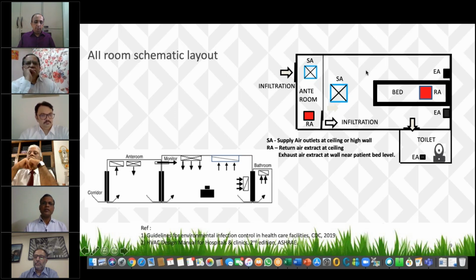But normally, hospitals have maybe 1 or 2 or 3 rooms which are designated and built to perform like an airborne infection isolation room. In today's case, where we have more cases, more patients requiring AII, that is airborne infection isolation, it may not be possible to bring all the patients here. So the ISHRAE COVID guidance document has given a methodology to convert a regular ICU or a regular patient room into a COVID patient room, whereby we stop the recirculatory movement of air and introduce exhaust air, and probably treat the exhaust air through HEPA filtration or by any other process, or release it at a large height well above the populated areas if HEPA filtration is not a viable option. So this option has been given there.